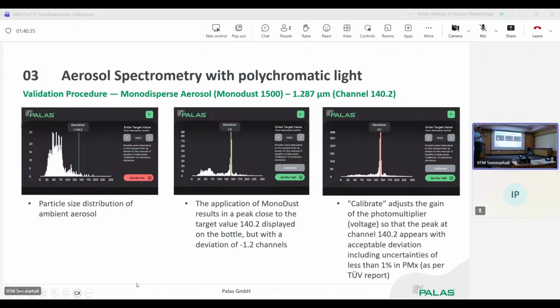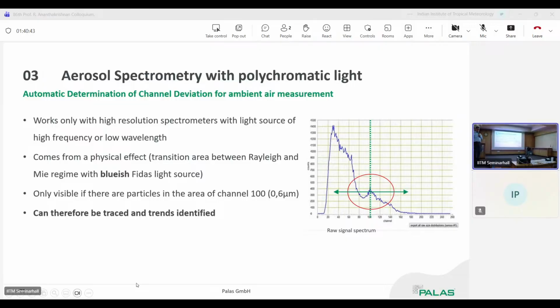which you can do again with monodust on site. We also have possibilities to see the drift of the system, especially with the bluish light of our Fidas regulatory monitoring system, but all the others which work with a bluish LED have the same appearance. Here you can see an anomaly in the spectrum. That's due to the Rayleigh-Mie transition area. And because it depends on the light source, it is always at the same point. This is the raw signal: if the system drifts, meaning the optics is spoiled or the LED source is decayed, then it breaks from this direction.